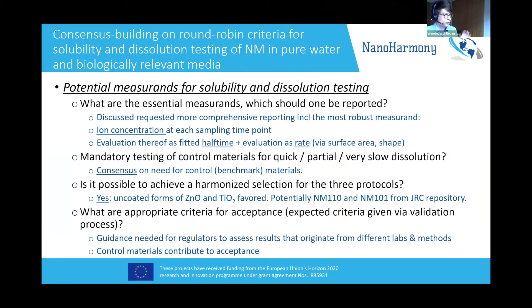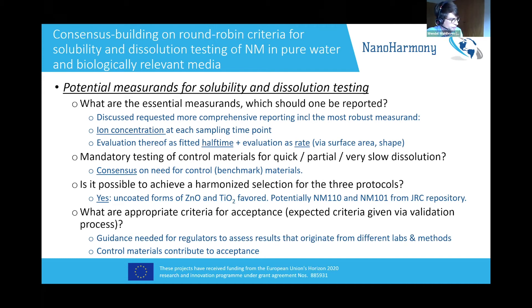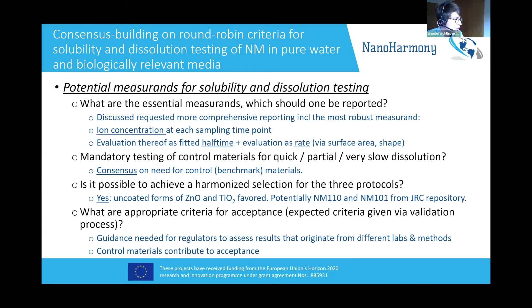Our discussion was mostly about how to organize the round robins — in black you see the questions, in blue you see the results. We asked what the essential measurements were and which ones should be reported. The group requested more comprehensive reporting, including the most robust measurement, which is the original ion concentration at each sampling time point. Additionally, one would report the evaluation of the data by a fitted half-time and by an evaluation as a rate, where the evaluation as a rate has very interesting material science implications because you scale by the available surface — but for that you need to know that surface, so it is more complicated and has more assumptions.